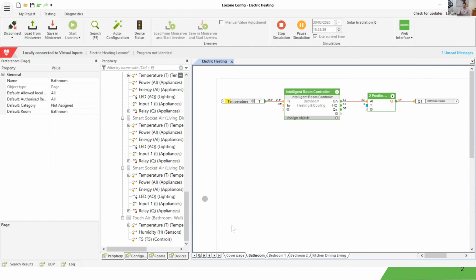But fundamentally, our heating with electric heating is all sorted and doing exactly what we need it to. If I drop that down to 20, so it's had quite a sharp takeoff, again, that output should go fairly high. And there we go, straight away, back to 10. And you can see that it's starting to learn what this room is doing and what the logic of this room is. Excellent. I hope you've enjoyed.